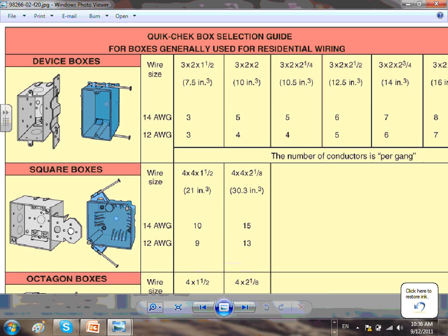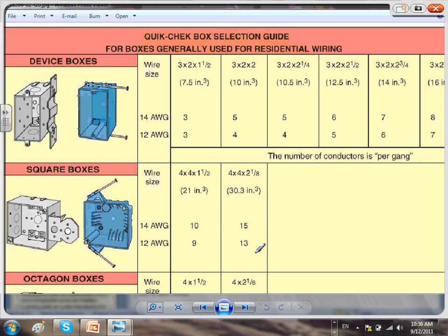One thing I want to mention, this is directly from the code. For example, reading this directly from the code: this single gang device box, if I have number 12 conductor, and this is the depth, I can put 3 conductors number 12. If I go deeper, I can put 4; deeper, still 4; deeper, 5; deeper, 6; and so forth. The deeper the box, the more conductors you can fit. Can you guys see that? They're all 3x2, 3x2, 3x2 - the only difference is how deep that box is.